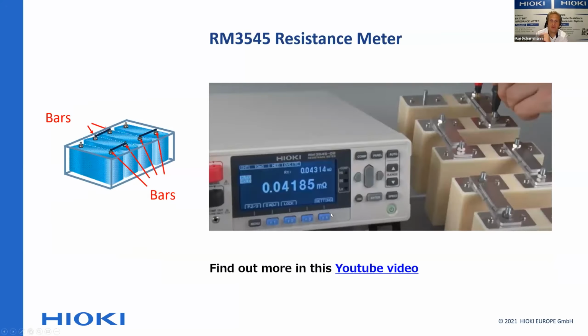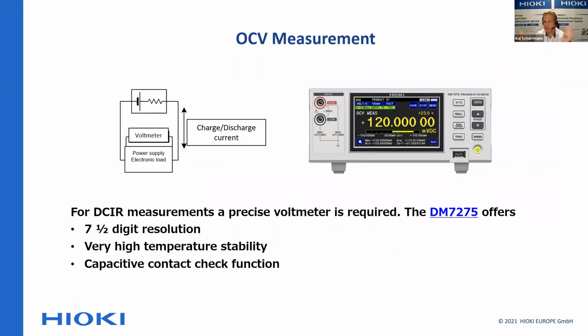Finally, we have this product again, the RM3545. We had it for tab welding, and I told you about the possibility to put in multiplexer cards. This is not only good for tab welding, but also very good for testing bus bars. If you're putting modules or cells together, you do that with bus bars, and again you want the smallest possible connection resistance. So this product comes in here as well. There's a YouTube video from HIOKI where you can find out more about this, but basically it's the same type of measurement as with the tab welds - just a bus bar measurement in that case.